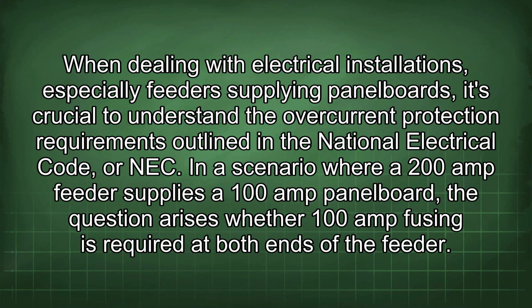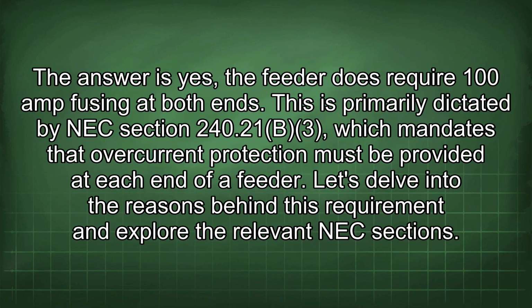When dealing with electrical installations, especially feeders supplying panel boards, it's crucial to understand the overcurrent protection requirements outlined in the National Electrical Code, or NEC. In a scenario where a 200 amp feeder supplies a 100 amp panel board, the question arises whether 100 amp fusing is required at both ends of the feeder. The answer is yes, the feeder does require 100 amp fusing at both ends.